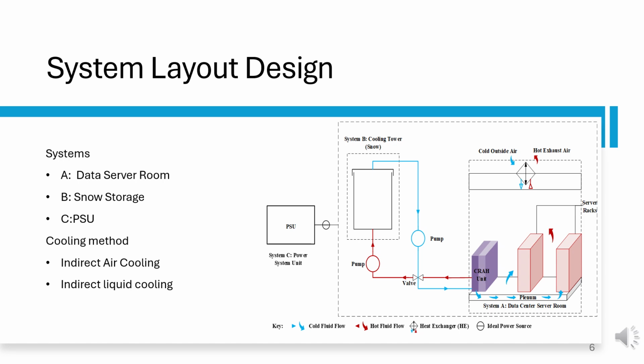Now, when it comes to system B, which introduces snow-based cooling, essentially we're using melted water from the snow, because as snow stays over time, it begins to melt. And how this works is snow collected during the winter is stored in an insulated containment area. We simulated the data center to be close to the Robin Hood Bay because it is a current dump site for snow in St. John's. Now, this melted water is pumped into the air handling unit of the data server room, where it absorbs the heat from the server room and circulates through to absorb the cold from the melted snow.